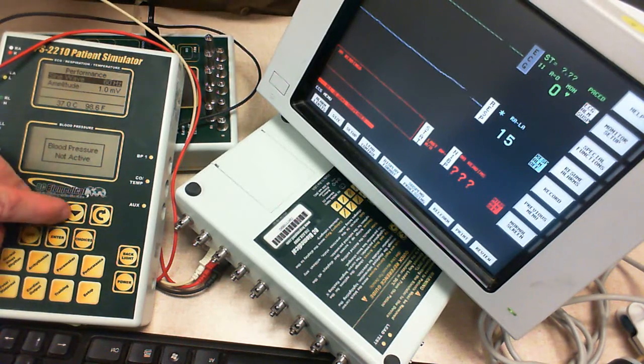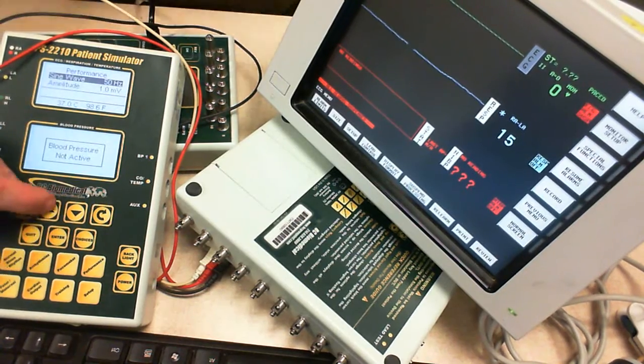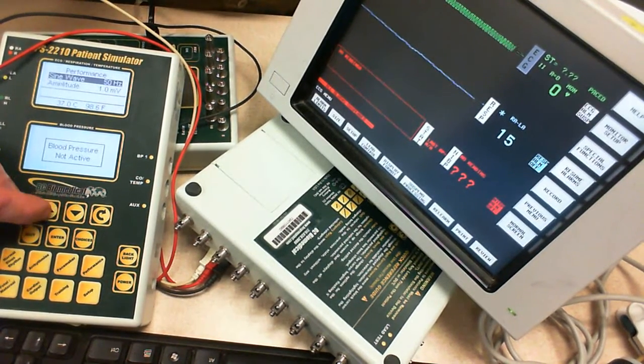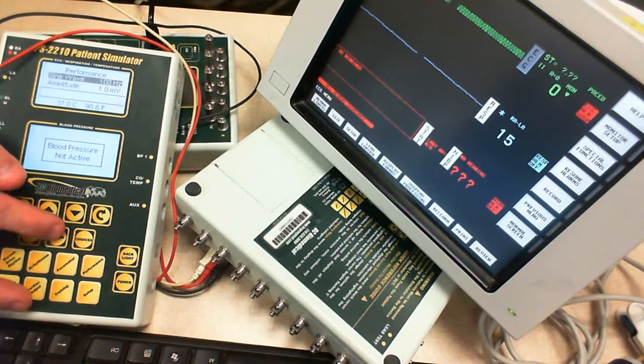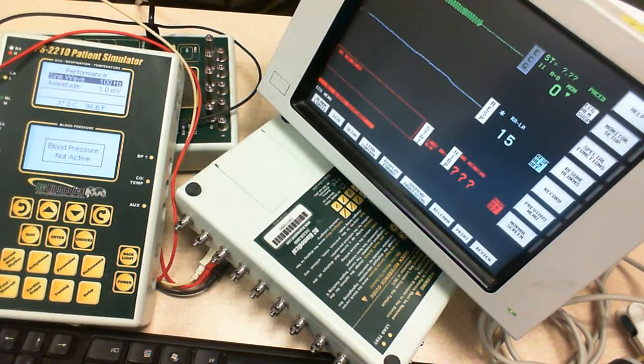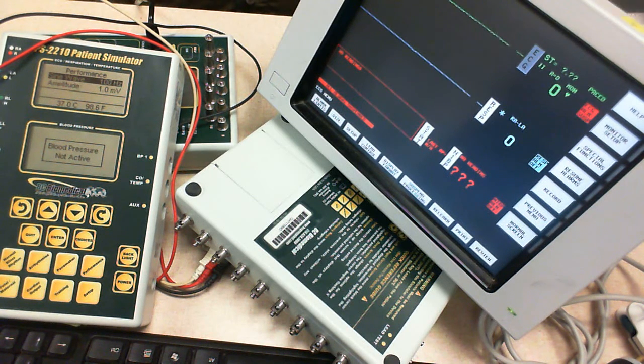Let's try the filter. I'm going to go back to 50 because we know we've got something at 50, and then I'm going to dial in 100. Notice how 100 went to nothing. So the 100 hertz works. So what would I say about this device? Fantastic for use in the U.S. I wouldn't use it in Europe or Japan because they use 50 hertz systems. Pretty much restricts this machine to North America. But you get the point, right?